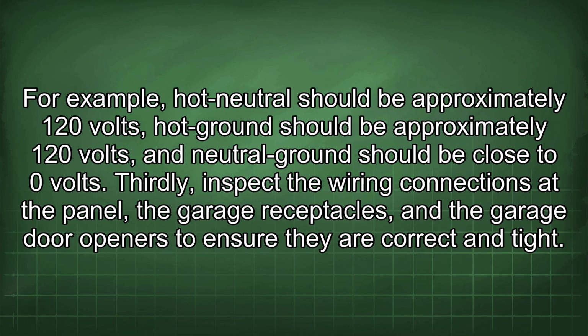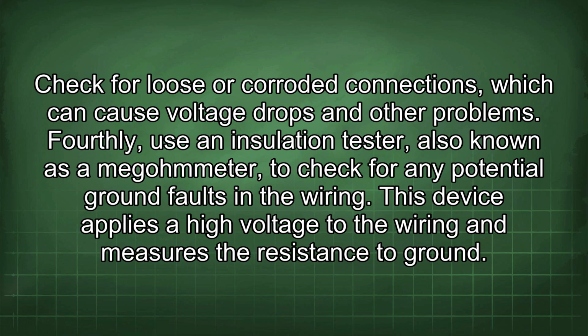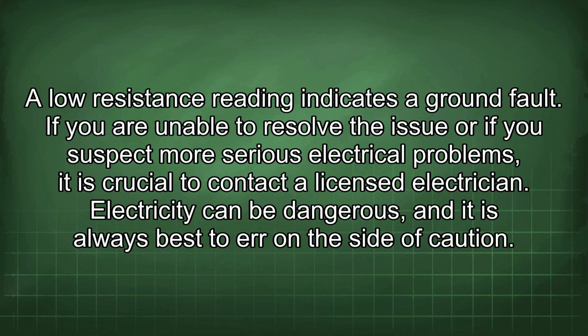Thirdly, inspect the wiring connections at the panel, the garage receptacles, and the garage door openers to ensure they are correct and tight. Check for loose or corroded connections, which can cause voltage drops and other problems. Fourthly, use an insulation tester, also known as a megohmmeter, to check for any potential ground faults in the wiring. This device applies a high voltage to the wiring and measures the resistance to ground. A low resistance reading indicates a ground fault.